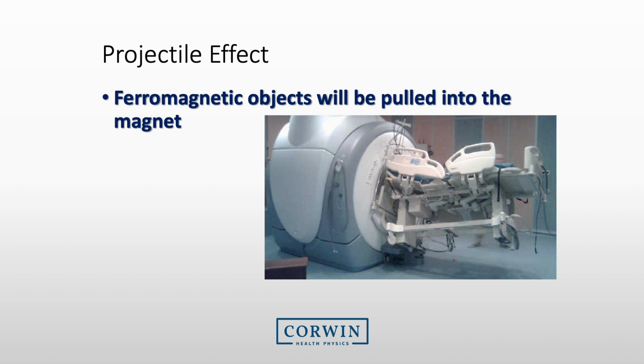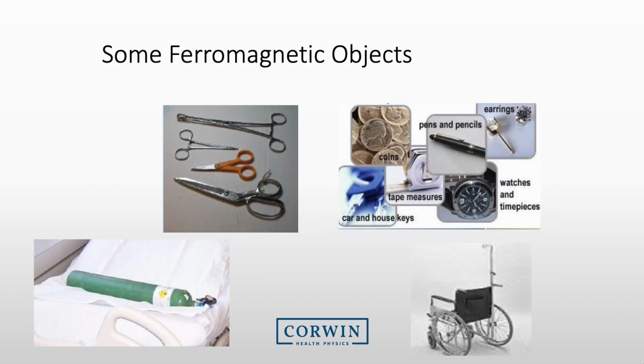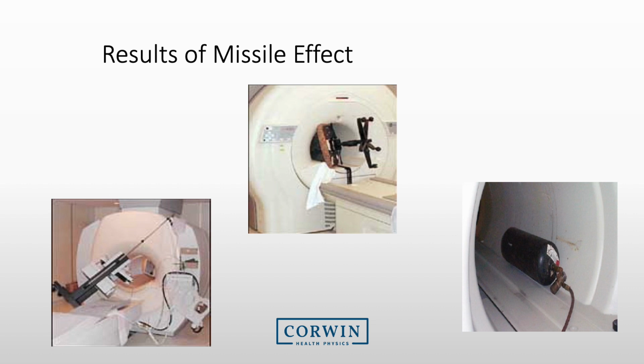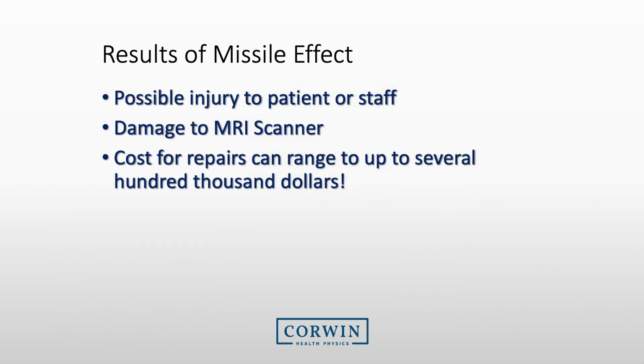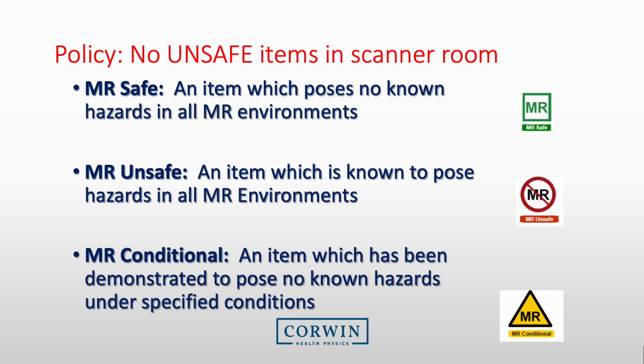As you are aware, the main concern with the magnetic field is the pulling of objects into the magnet. Here is an example of the wrong bed being brought into the MRI suite. Please be aware of many common ferromagnetic items in the hospital. All of these items and more need to be prevented from entering the MRI suite. As many of you are aware, there are serious consequences of these ferromagnetic objects entering the room. These objects cause significant injuries to patients or staff, and they damage the MRI system significantly. So because of this extreme magnetic field, we have a policy that no unsafe items enter into the MRI room.